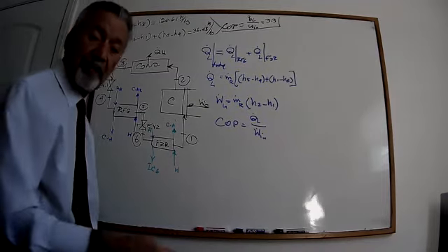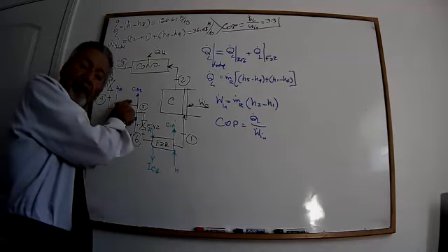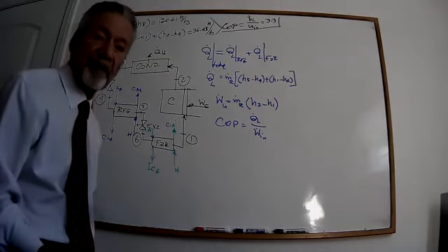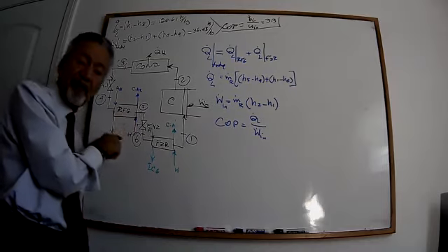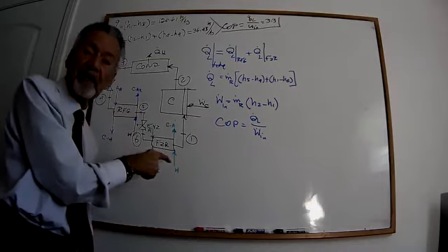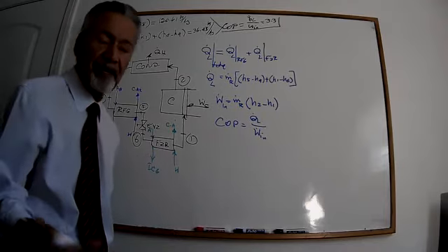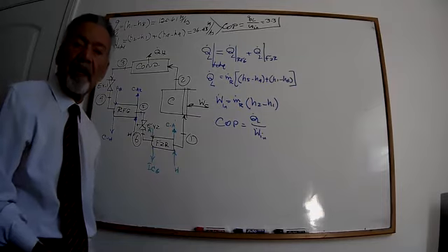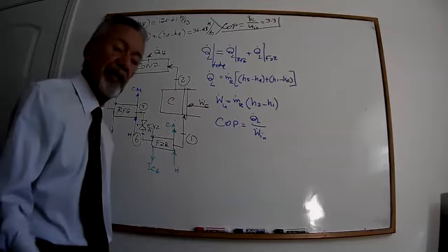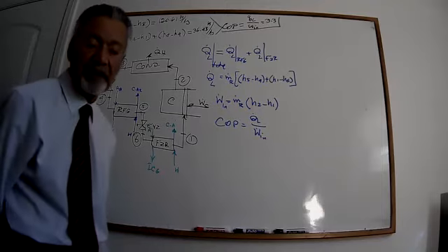But we learned that we can be more energy efficient because this is already cold, already at, let's say, 48, 49 degrees Fahrenheit. It's easier going from 48 to 25. But if outside temperature is 80, well, in a house it's about 75, 78. Going from 78 to 25 uses a lot of energy. That means the compressor has to be larger and uses more electricity.